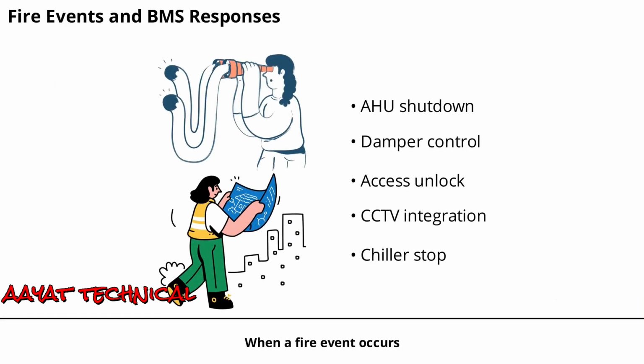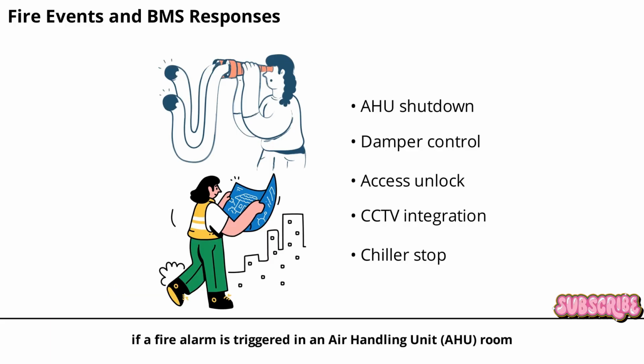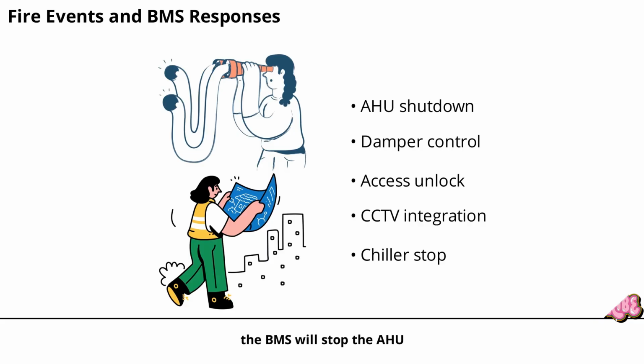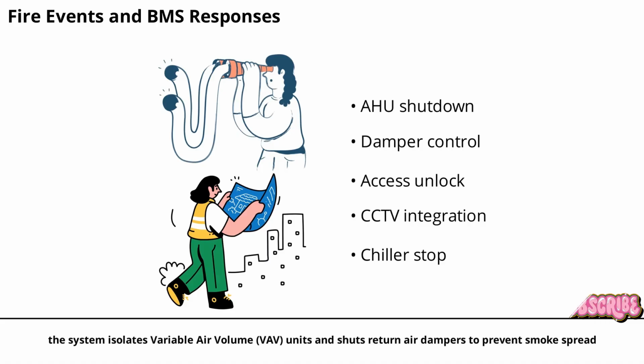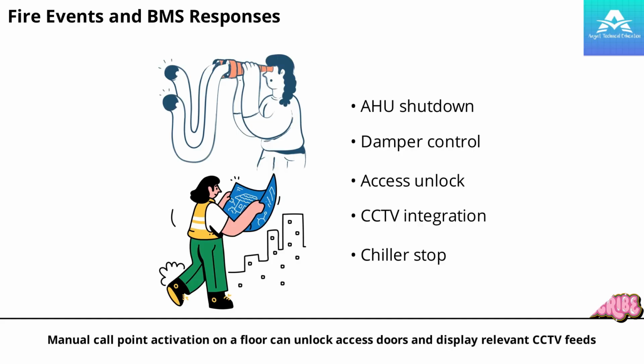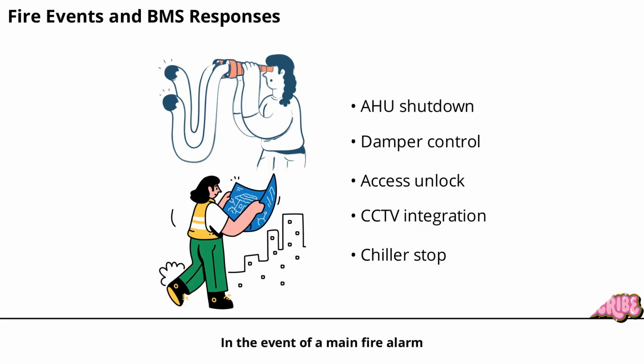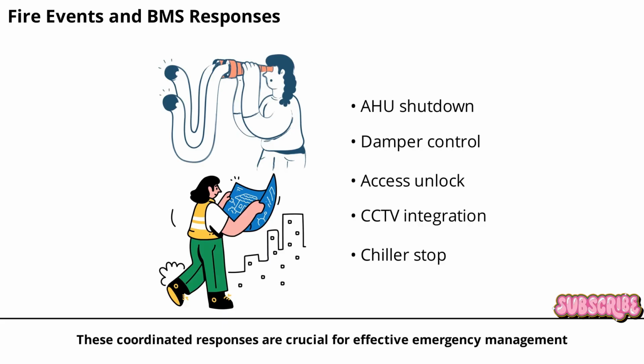When a fire event occurs, the BMS springs into action. For example, if a fire alarm is triggered in an air handling unit (AHU) room, the BMS will stop the AHU, close dampers, and display an alarm pop-up. If smoke is detected in a specific zone, the system isolates variable air volume (VAV) units and shuts return air dampers to prevent smoke spread. Manual call point activation on a floor can unlock access doors and display relevant CCTV feeds. In the event of a main fire alarm, the BMS can stop chillers, disable elevators, and send alerts to operators and security teams. These coordinated responses are crucial for effective emergency management.